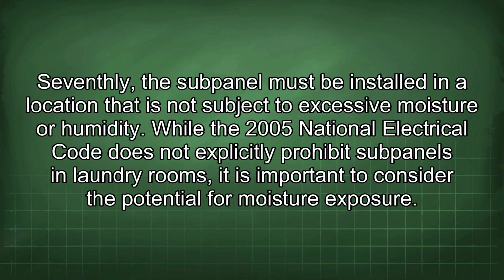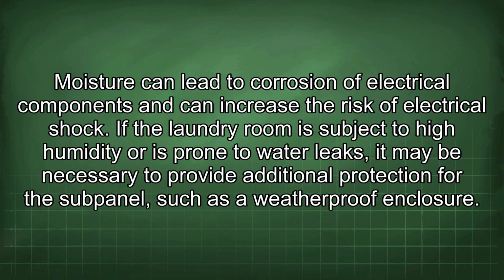contact. Seventhly, the subpanel must be installed in a location that is not subject to excessive moisture or humidity. While the 2005 National Electrical Code does not explicitly prohibit subpanels in laundry rooms, it is important to consider the potential for moisture exposure. Moisture can lead to corrosion of electrical components and can increase the risk of electrical shock. If the laundry room is subject to high humidity or is prone to water leaks, it may be necessary to provide additional protection for the subpanel, such as a weatherproof enclosure.